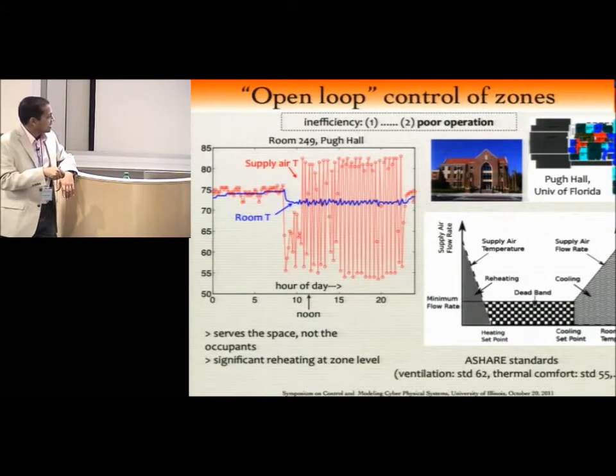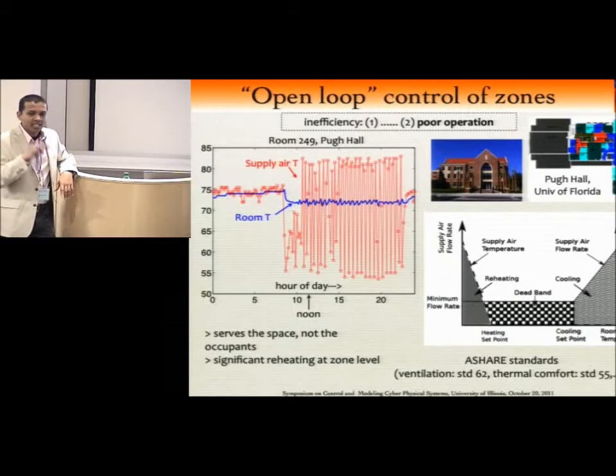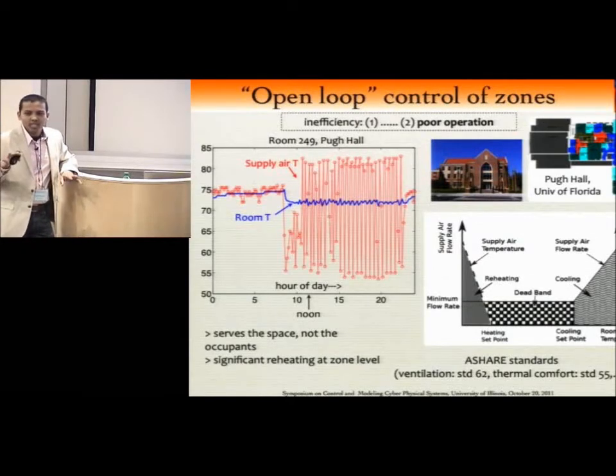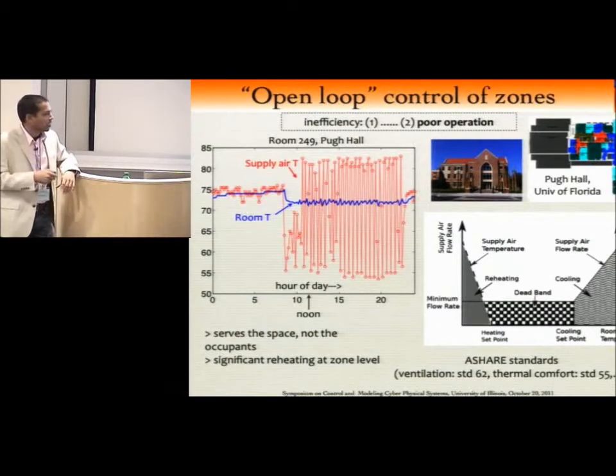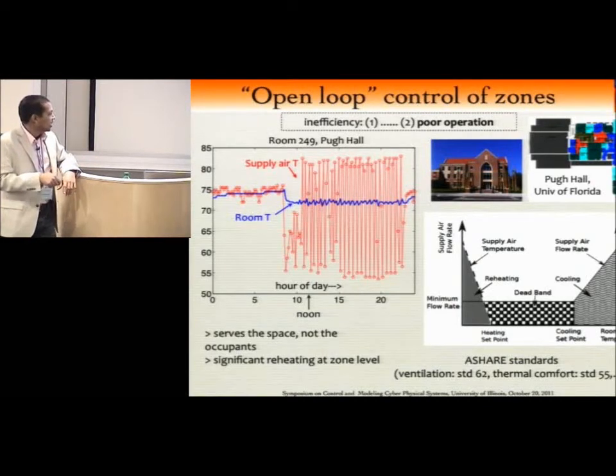If the temperature starts increasing, it increases the flow rate of air, because the nominal supply air is at low temperature, 55 degrees Fahrenheit usually. That varies though. And it goes on increasing until it reaches the maximum it can, because every piece of equipment has some saturation level. After that, it just keeps supplying at maximum. It cannot do much more. On the other hand, if it starts becoming really cold, then it reduces the flow rate only down to the minimum, and after that it starts reheating the air, as much as it is capable of reheating. So ideally, this is what it should be doing to maintain temperature.